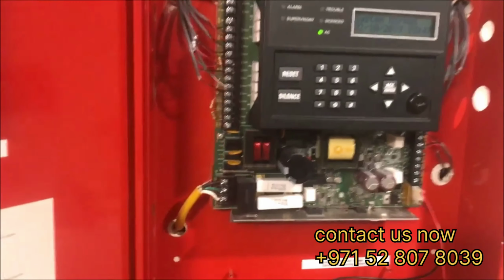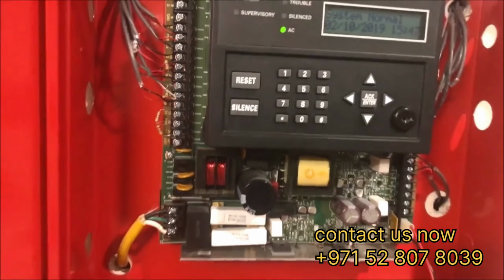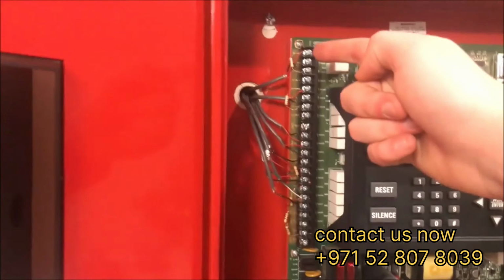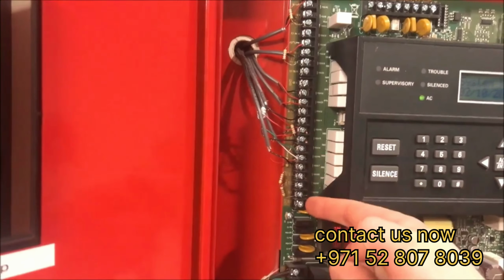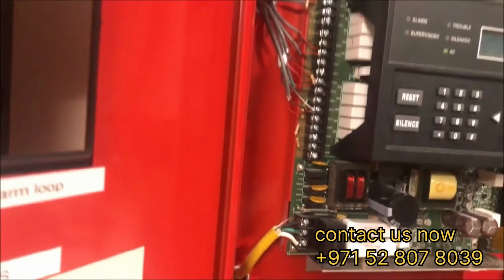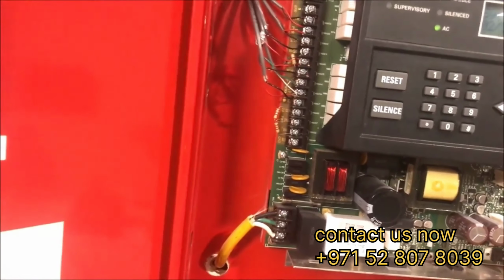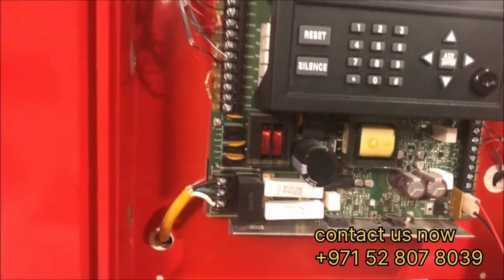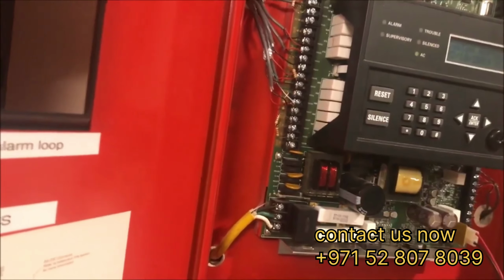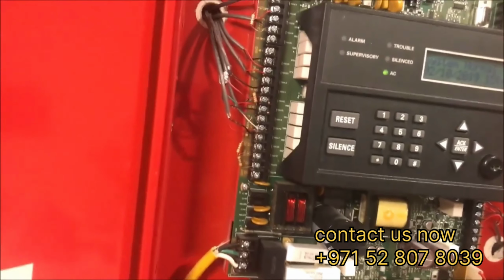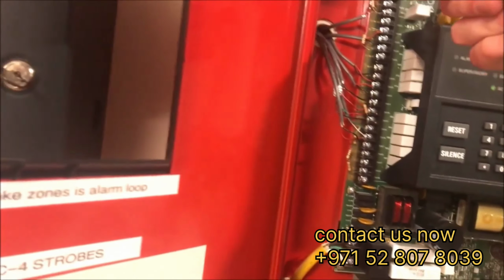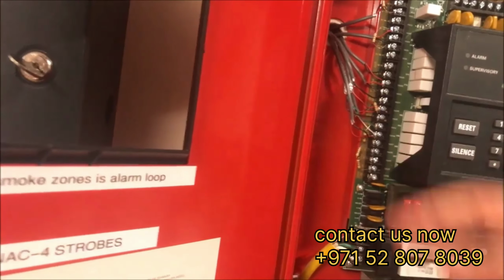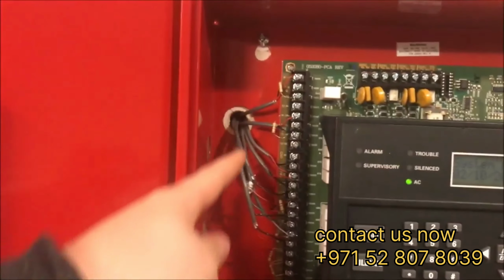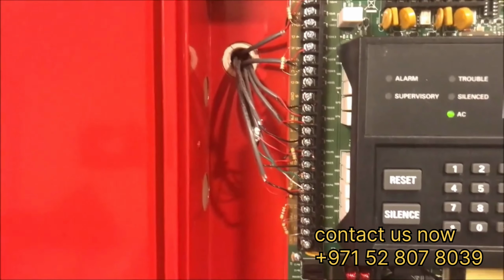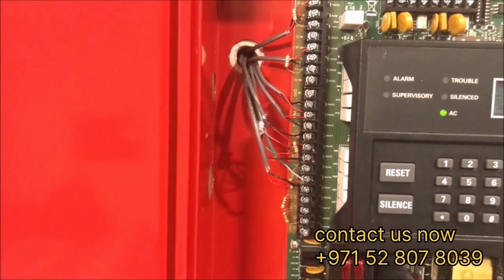If we open it up, one of the many characteristics of a conventional fire alarm control panel is just huge, long terminal strips with lots of resistors and lots of wires. Now in a real setting, resistors would be out in the field, but because this is a hobby system, I have my resistors in the panel so they don't get broken while changing pull stations. So that is a huge characteristic that will help you know that it is a conventional panel. It's just one big or a couple big terminal strips going down, because this is your SLC side. This is your signaling line circuit. These are where all your initiating devices are going.